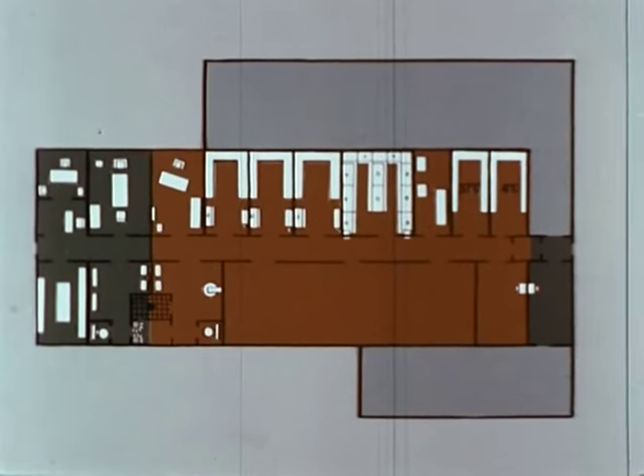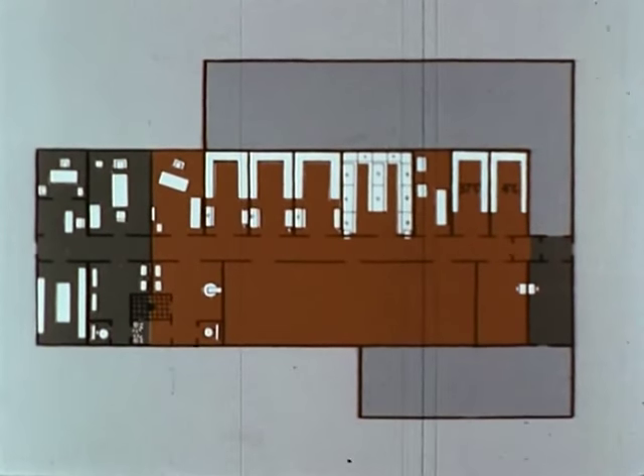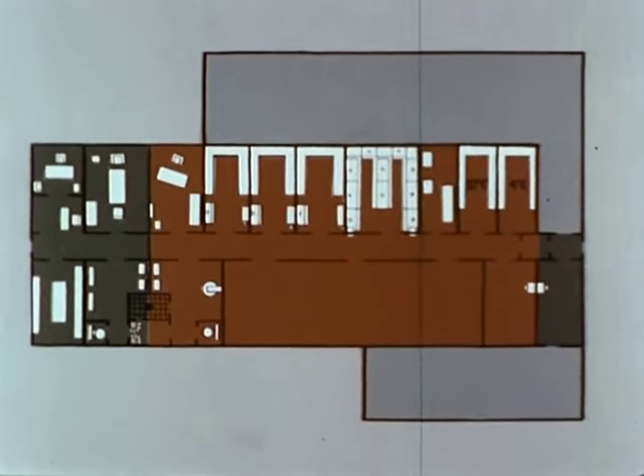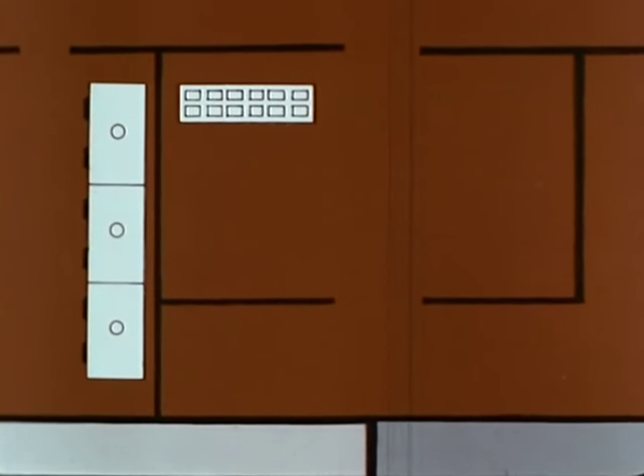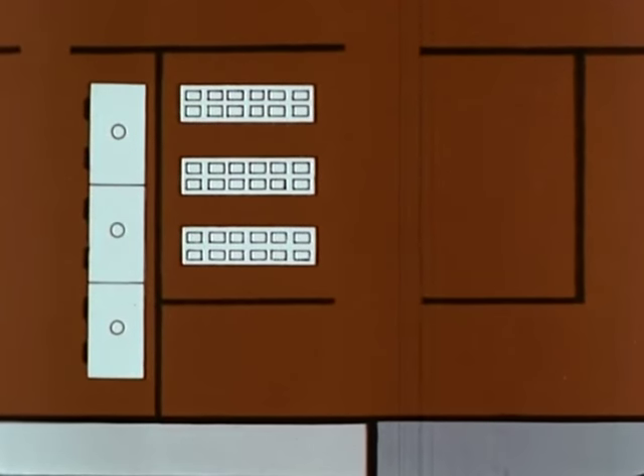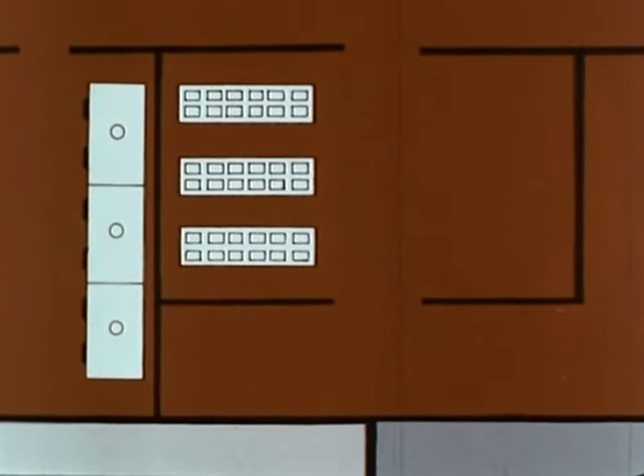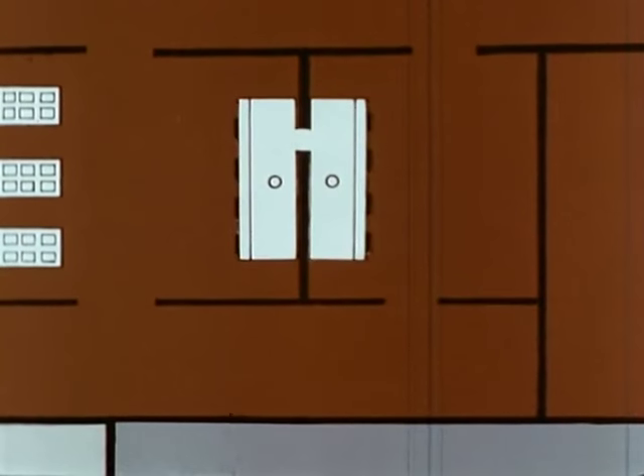The third functional zone in a standard facility is the research area for both small and large infected animals. This usually includes laboratories having appropriately ventilated cabinets for inoculation and autopsy, and animal rooms equipped with such isolation equipment as ventilated cages and UV cage racks. In some instances, it may be desirable to locate in a room adjoining the animal room aerosol exposure equipment, such as the Henderson apparatus.